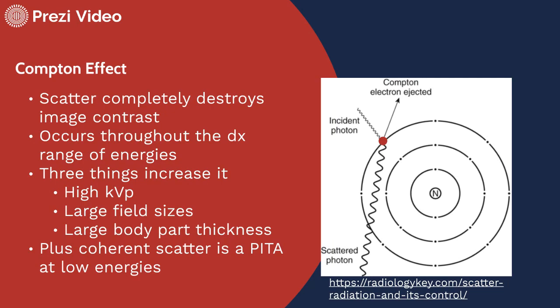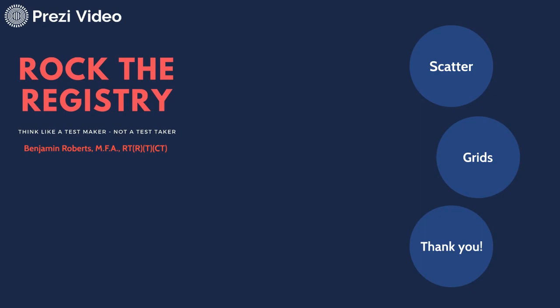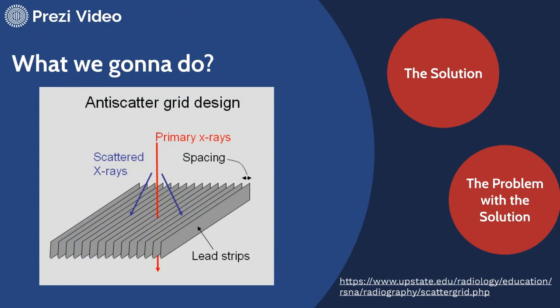And if we wonder what exactly is happening at that point of interaction, we can zoom in here and see — well, that's where grids step in. I love that this illustration calls the grid the anti-scatter grid — it just sounds awesome. Basically, this thing works kind of like the bouncer in a club. It allows primary x-rays to pass through the spacing material, but any scattered x-rays are going to be caught by the lead strips. You can think of it like a comb — we're combing through the x-ray beam, allowing straight rays to pass through, while angled scatter is caught by the lead strips.